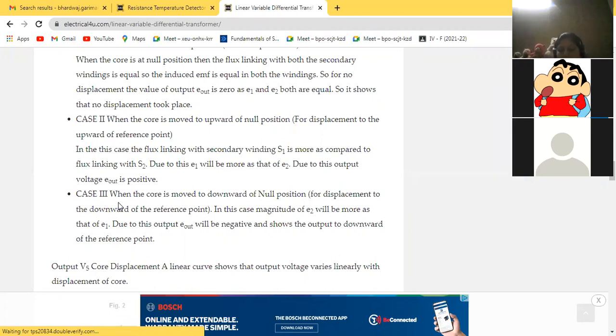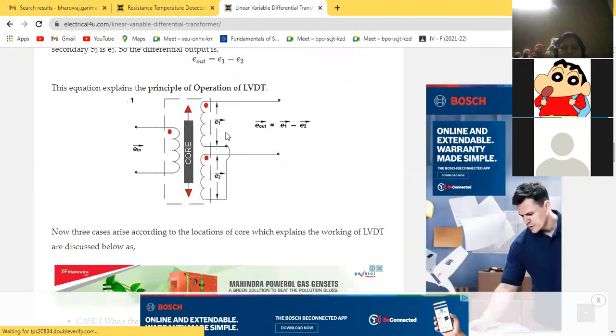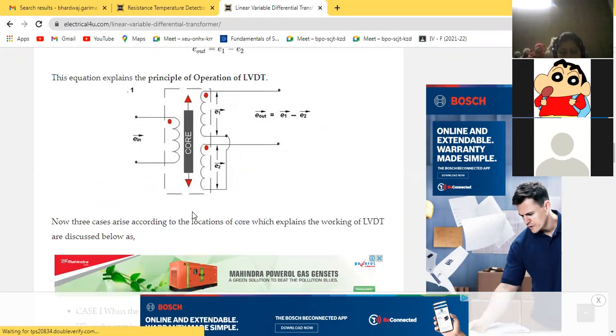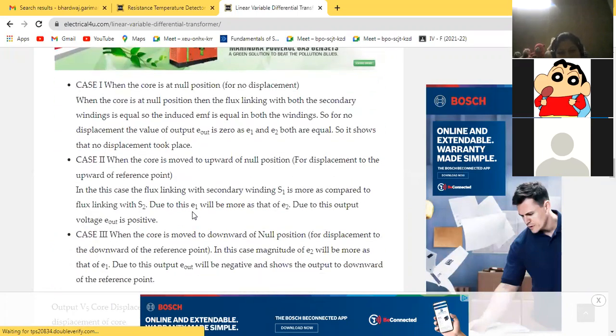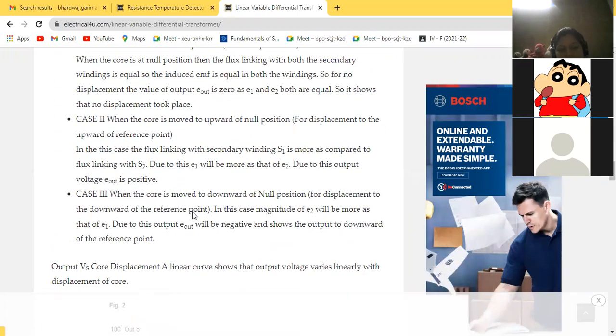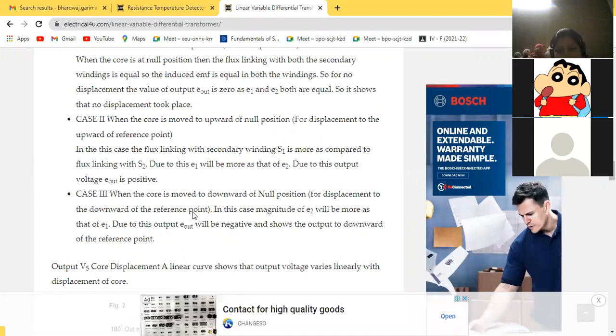Where will it go if it goes upward, okay? And if it goes downward towards E2, then let's see what the case is. Now in case 3, when the core is moved to the downwards of null position for displacement to the downward of the reference point, in this case, magnitude of E2 will be more than that of E1. Due to this, output E out will be negative and shows the output to downward of the reference point.